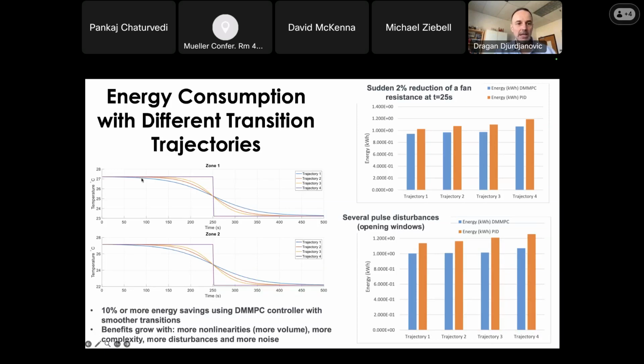So what was very interesting was that we can optimize the trajectory that we wish to execute while we are going with temperatures from temperature 1 to temperature 2, and formally drive those two temperatures in zone 1 and zone 2 to desired levels with increased savings. So you can see that different trajectories are leading to different energy consumptions. So the message that I wish to give is, utilize these advanced control techniques, especially given that you're adding so much exciting equipment into HVAC systems, especially when you're doing it with large volumes like airports, sports arenas, where nonlinearities and flows are bigger, and therefore PID controllers, or linear controllers, are less and less efficient.